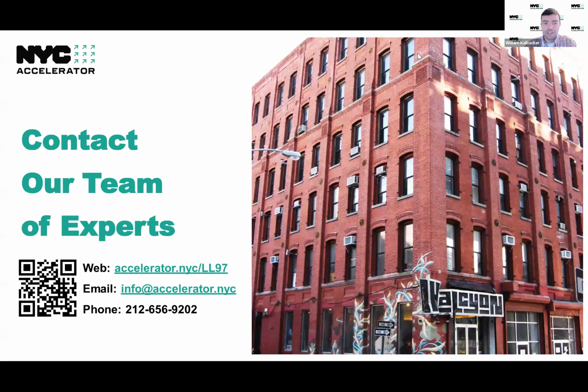I was just going to jump back to the list here. Okay. Item number 4 is installing individual temperature controls, and number 7 revolves around system sensors. So individual temperature controls are going to basically inform the actual unit itself in the apartment to control the heat that's being released by that terminal unit in the apartment. Number 7 is basically about informing the central plant. So you want to have feedback to the boiler in the basement or the equipment in the central plant to tell the system centrally that the apartments are fine. You know, there's enough heat in the apartment so that the boilers can modulate down or they can turn off. So it's basically about holistically overheating the building versus making sure that the apartment itself is not overheated. That's really the difference between measures 4 and 7.